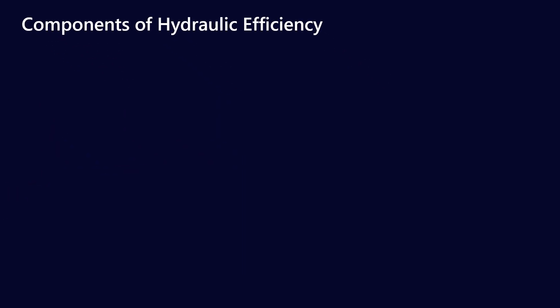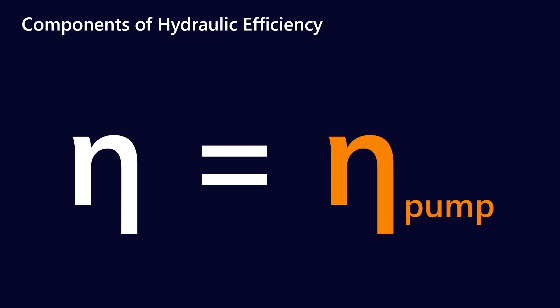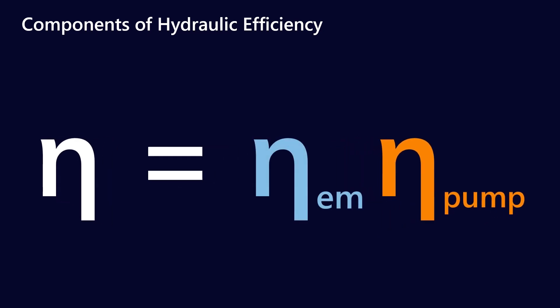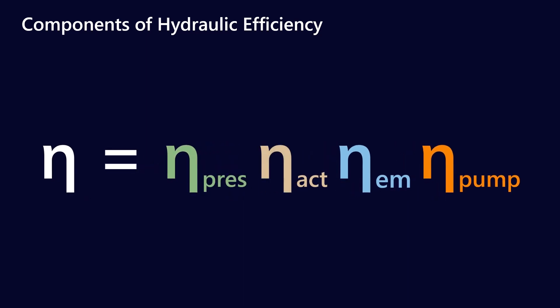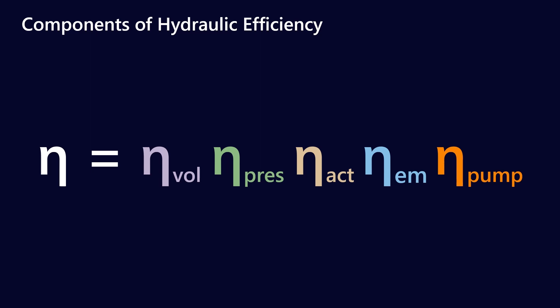Most of the time when we talk about any efficiency term we've represented it by this Greek letter eta. In hydraulic packs, first we have to consider the mechanical efficiency of the pump, which is probably driven by an electric motor so there's some inefficiencies there. Then we've got the losses due to the actuators in the hydraulic pack, and then we have how much the pressure translates through the system as well as how much the volume translates through the system. One of the dominant terms when it comes to hydraulic efficiency is actually the mechanical efficiency or the overall efficiency of the pump.